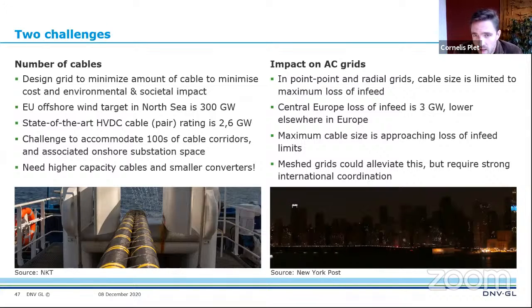On top of that, you also have to add interconnection targets. Looking at state-of-the-art HVDC cable ratings, which is inching towards 3 gigawatts, you can see that we need hundreds of cable corridors and hundreds of associated onshore converter stations. To minimize the impact on surrounding countries like the Netherlands, it's really important that we work toward higher capacity cables and smaller converters.